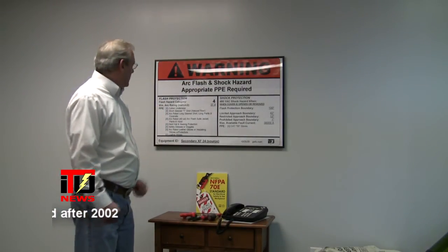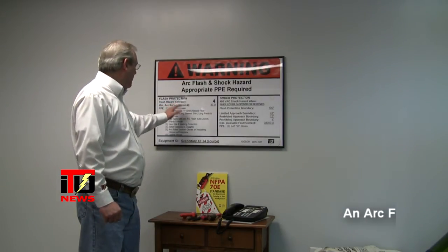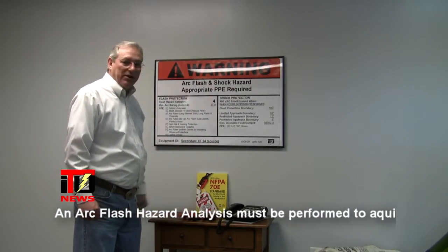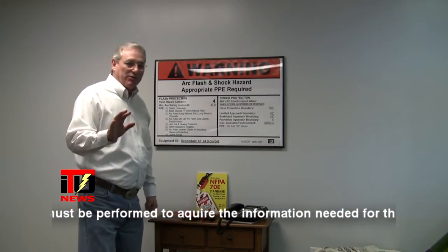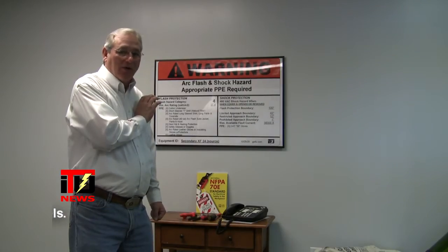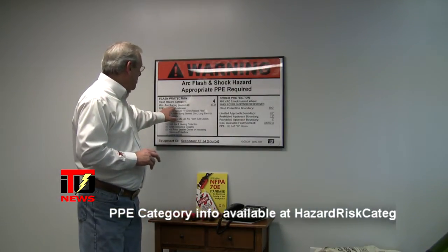As we travel down the left side, we see the flash protection and the flash hazard category, sometimes referred to as the HRC. In this instance it is a category four. What that's referring to is, if you're going to be working on the equipment this is labeled for, you must use a category four arc flash suit — a 40 cal suit you might hear. The 40 cal comes from the next line where it talks about the minimum arc rating in calories per centimeter squared. In this instance it's 37.9.